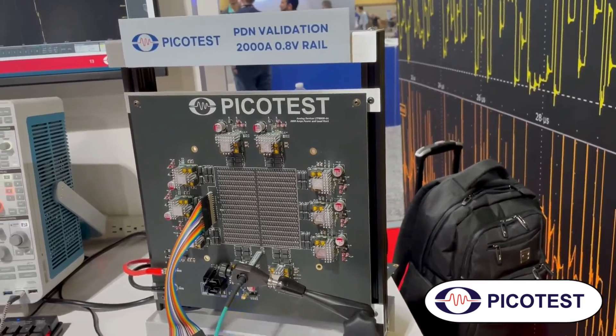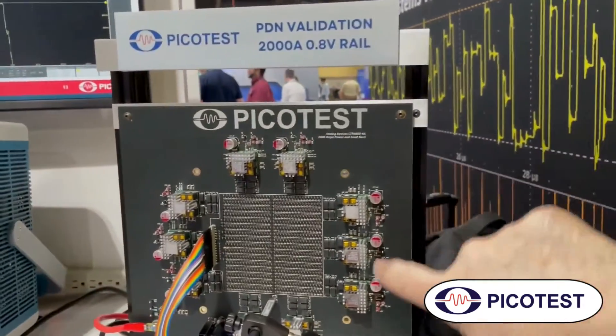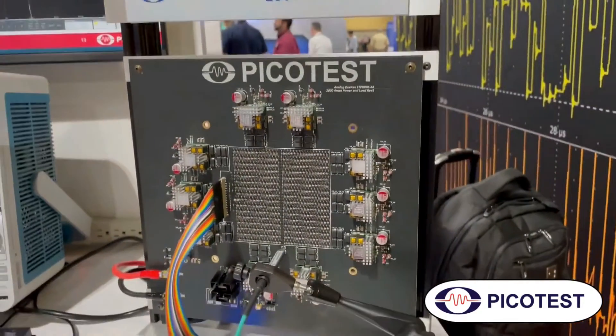Steve, who is very good at solving such problems, is going to explain about this board and some of the components on it and how you do the measurements. We have customers mostly from the data center and AI world, and their processors are getting really dense. They've been asking us for a couple of years if we could build a device that would allow them to test their power rails ahead of the actual delivery of an ASIC. It takes a long time to develop the ASIC.